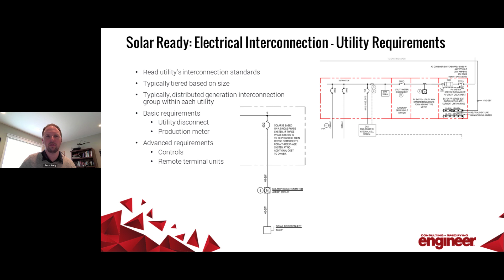Finally, if you're preparing a solar-ready deliverable, my recommendation is, on a roof plan with the architectural and electrical, show the proposed area clearly. You don't have to do a full layout necessarily. On the electrical plans, clearly indicate the pathway from the rooftop to your point of connection, and show that on your single line diagram as well. Finally, add a performance spec to indicate your intended function, system size, and so on. You don't need full construction documents, because every different module and inverter combination requires its own different engineering.